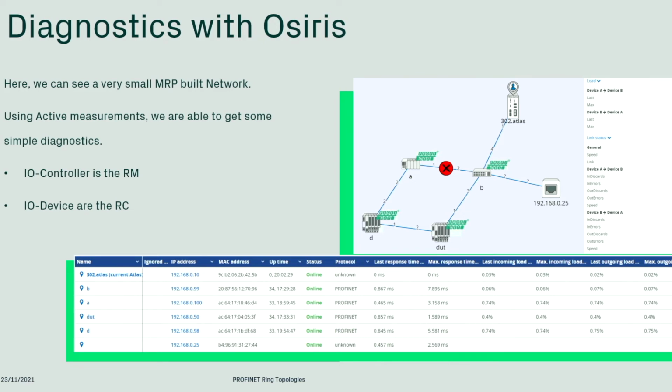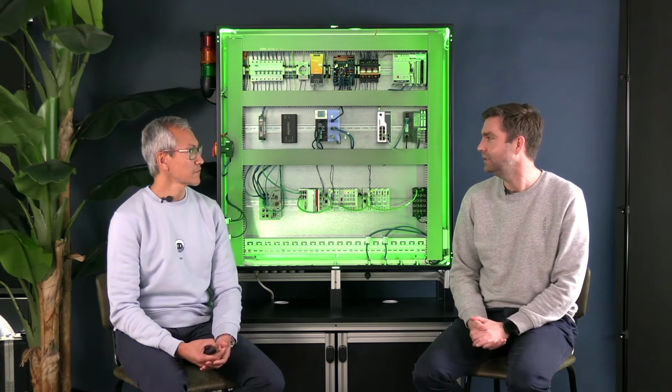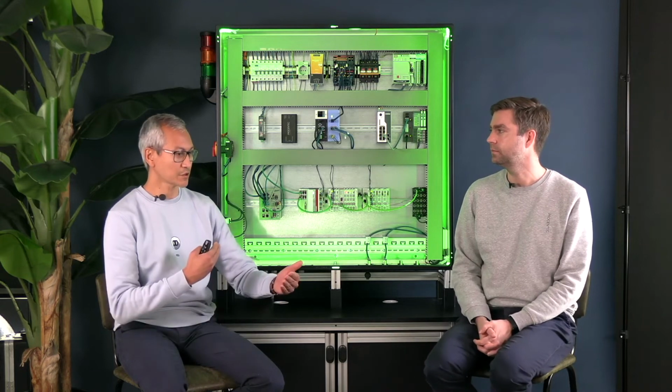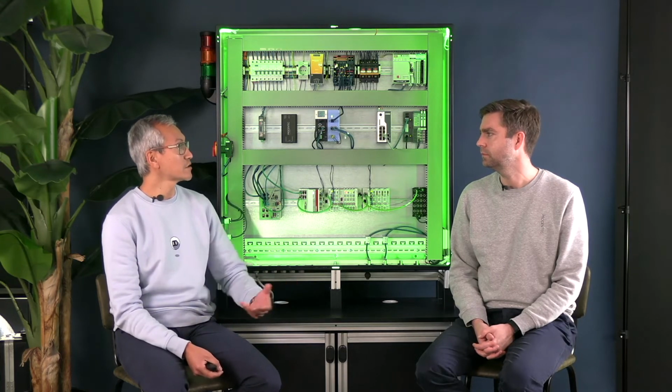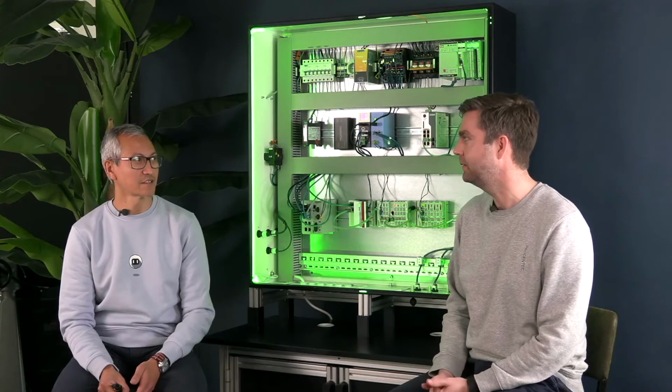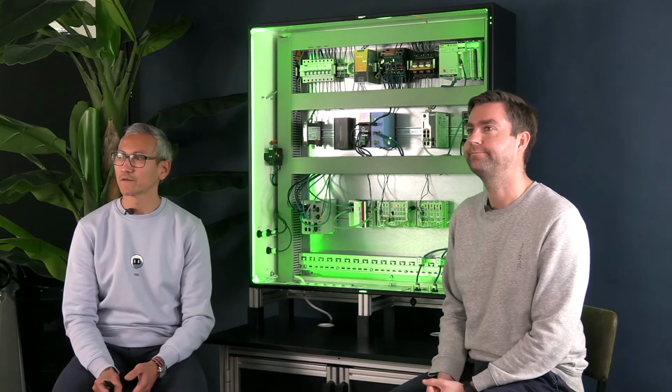Okay, so with unmanaged switches, you don't get enough information to understand how your ring is structured. No. And I'm guessing it wouldn't even have the media manager, the ring manager on there. Exactly. An unmanaged switch is just putting through all the messages and it cannot configure anything in it. It can also not give you information about its ports. And if you want to monitor and maintain your network correctly and reduce downtime, we always advise using these managed switches. Yes. Okay. That's very important.